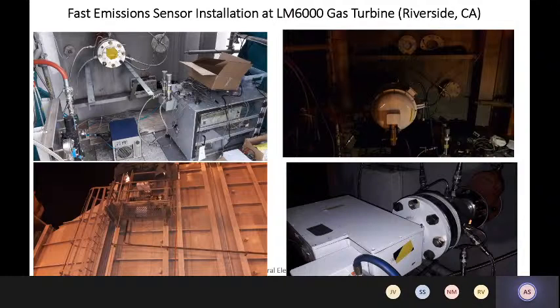So you have electrical cables that are going down to the control room, where we do advanced signal processing in order to back out the concentration information of the gases in real time. That gas concentration information is then converted into the Ethernet global data communication protocol format, and then pushed out to the Mark VIe controllers that are actually used to control the gas turbine and adjust the water injection appropriately. Next slide.